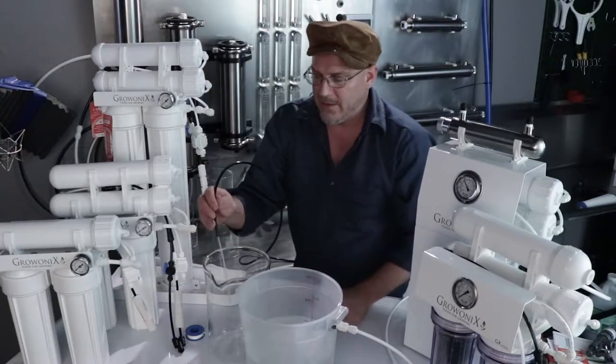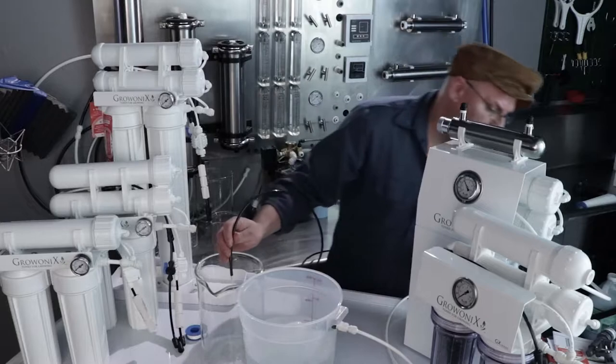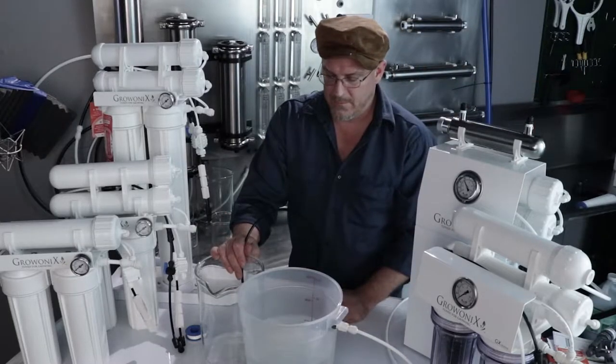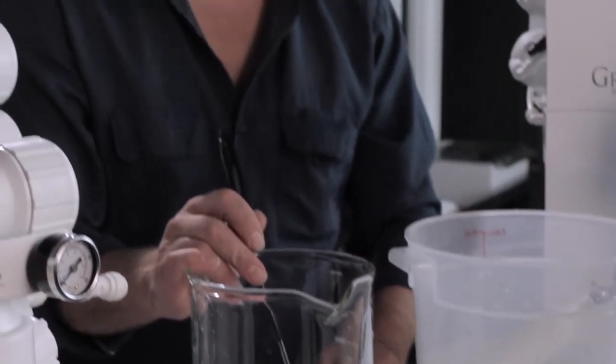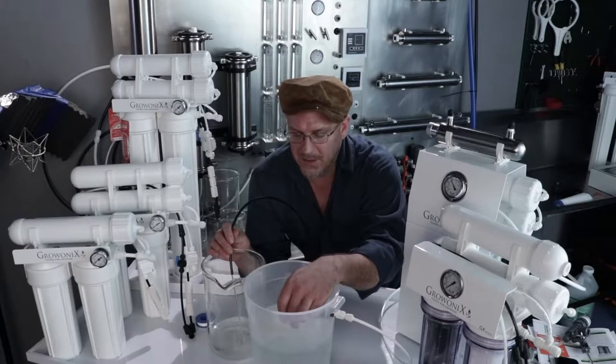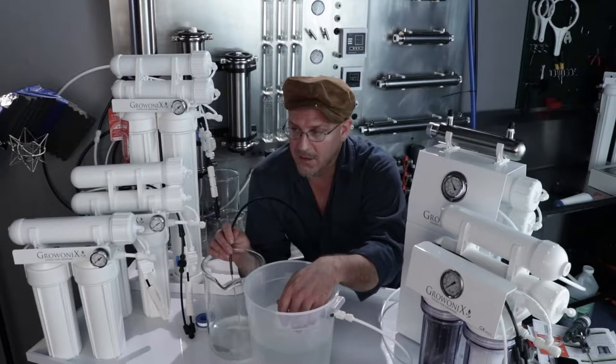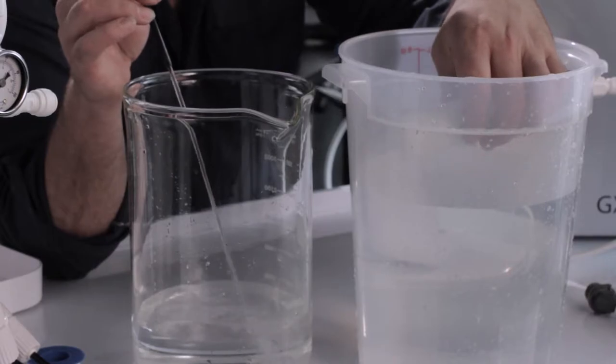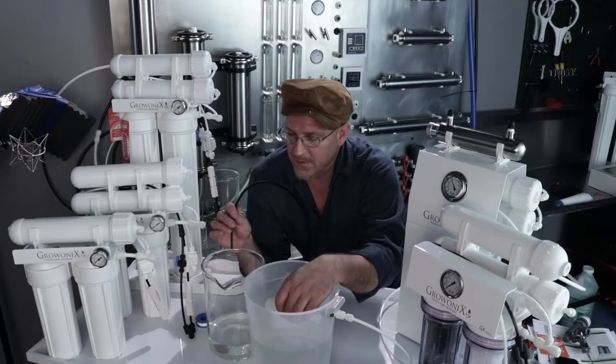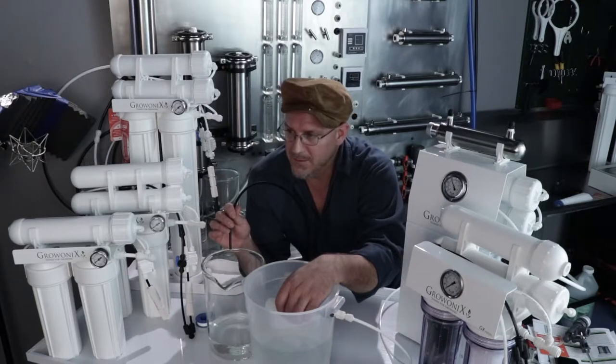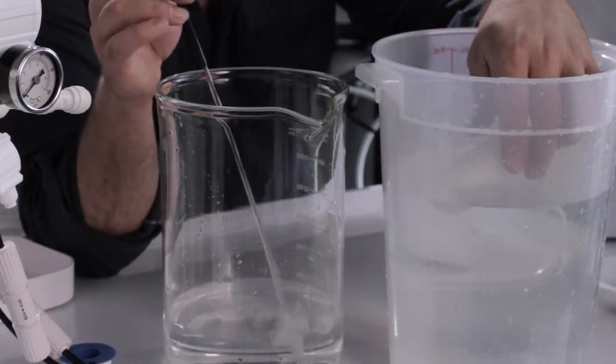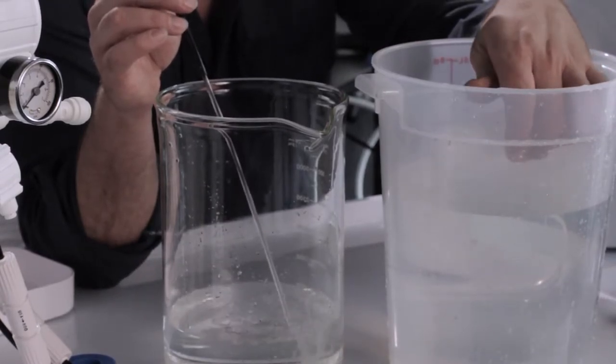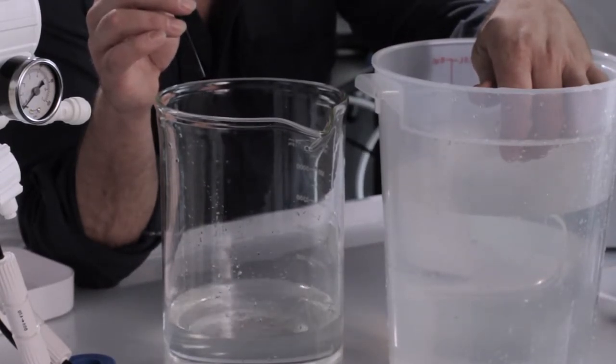Now I'm going to grab the drain line of the GX 400, which is right here. I'm going to show you how the float valve and the auto shutoff valve work in conjunction with each other. If I artificially manipulate this valve and pick it up, closing off the permeate stream, the drain water is going to shut off. And if I lower the valve, reducing the pressure in the permeate line, the auto shutoff valve is going to open up again, and the drain water will flow. So valve up, valve down.